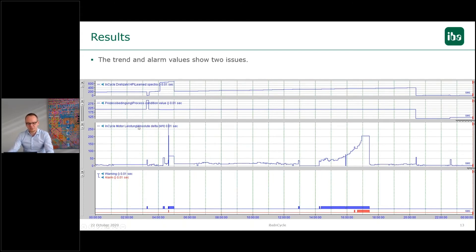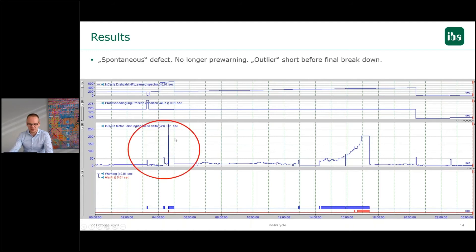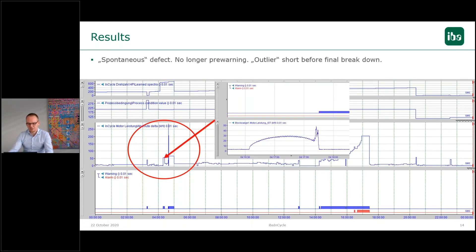What we can see here is what you saw before in live online in PDA — this absolute delta value. We were monitoring this absolute delta value, and based on this value we configured a warning and an alarm. What we can see here during this event is that there was a breakage of the blade where several teeth broke out.